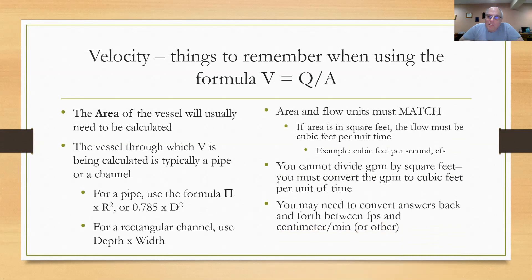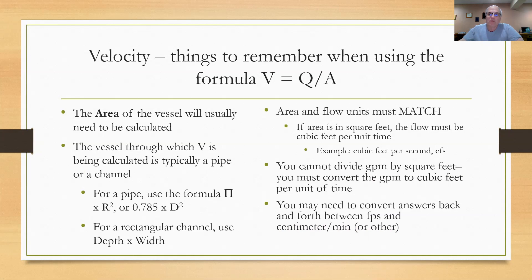In these equations, the area and the flow units have to match. If the area is in square feet, the flow has to be in cubic feet per unit of time, typically cubic feet per second or cubic feet per minute. You cannot divide gallons per minute by square feet. You got to convert first. In this case, convert the gallons per minute to cubic feet per unit of time. Your units of flow and area must match in order to do this equation.